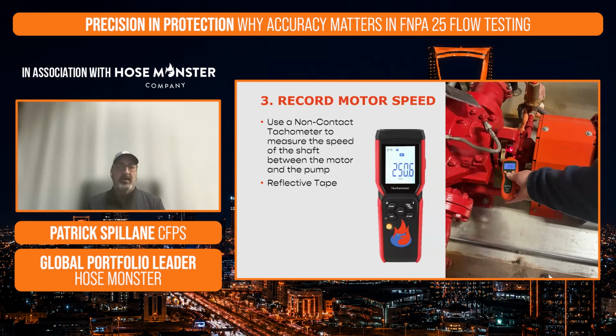And after we record our fire pump pressures, we now need to document how fast is that fire pump spinning, right? We're going to be measuring the speed. And we do this by putting a piece of reflective tape on the shaft between the motor and the fire pump itself. So here we can see it's going to be right next to, on this pump, it was right next to the packing gland, and we're going to use a non-contact tachometer, a laser tachometer, to count how many revolutions a minute as that fire pump is spinning. So what it's doing is that laser is bouncing off that reflective tape, and so as the shaft is spinning, the meter there counts how many times per minute that fire pump is spinning.